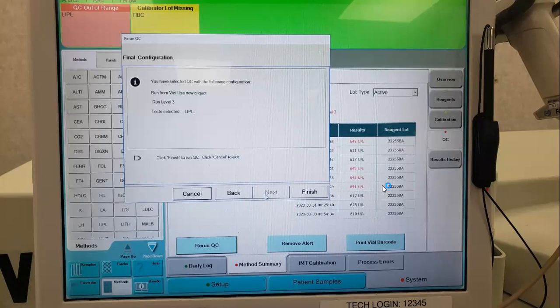Sometimes the flex packs are getting to a few of the last tests, and with QC they will run a little bit funky, especially if they're tests that we don't do often enough to use the flex packs quick enough. Sometimes they have already punctured the top of the reagent and they haven't been used that day, and so the reagent that is in there starts to degrade, and so taking off the reagent flex pack and putting it back on will make the machine go to the next aliquot section. And if the reagent pack has all the holes punched in the top and it's almost out, we're just going to discard that in the biohazard and put on a brand new one. That's what we're going to do second.